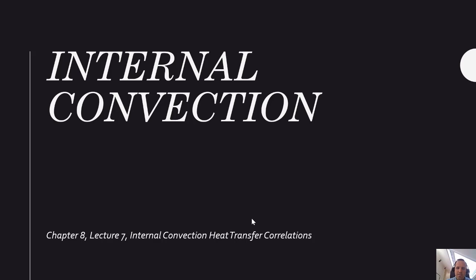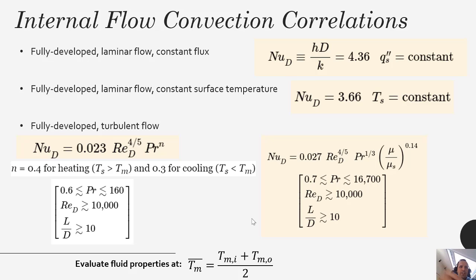There are various combinations and configurations, so calculating the Nusselt number and your H, your heat transfer coefficient, is still a relevant topic here. For internal convection, when you have fully developed laminar flow with constant flux, your Nusselt number ends up being a constant 4.36.